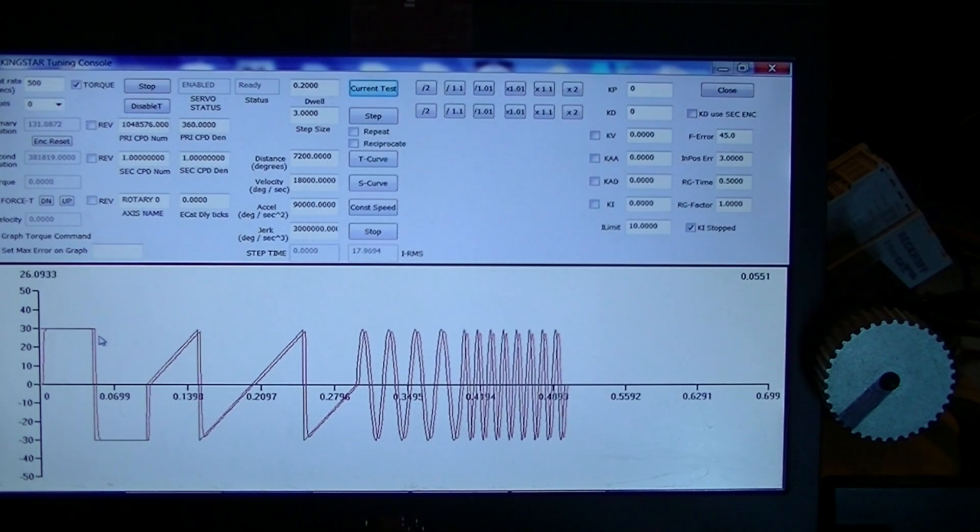We were asking for 30% as a flat 30%, then minus 30%. We have a couple of ramps and a couple of different sine waves. If the red, which is the torque actual from the drive, doesn't match the black commanded, then you have a problem and there's no point in trying to set up a servo. In this case, you can see it is following it. There's a little bit of delay, a couple of milliseconds, that's the natural part of an EtherCAT network. But all in all, this is good.